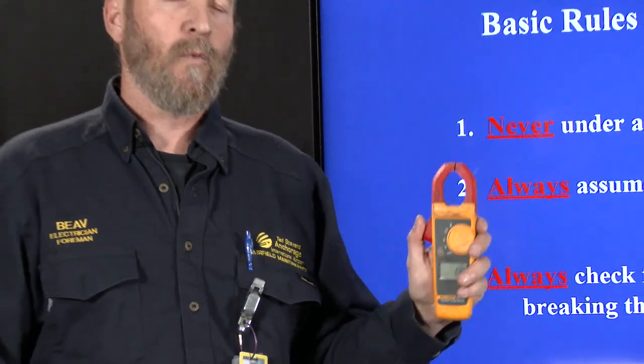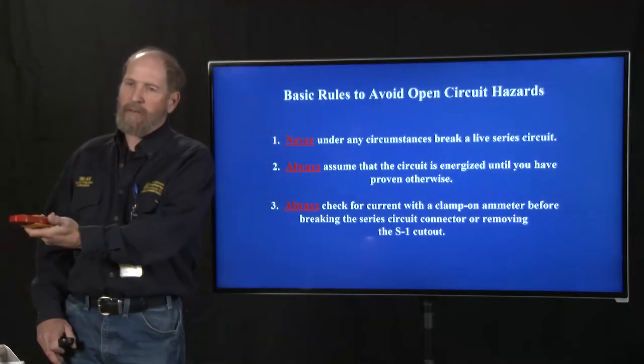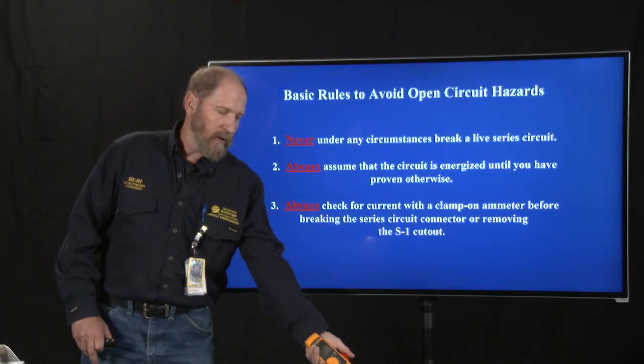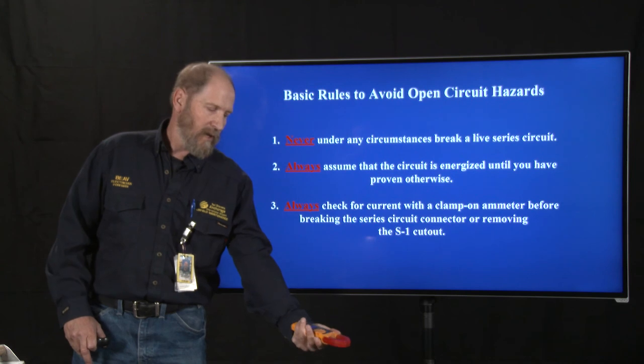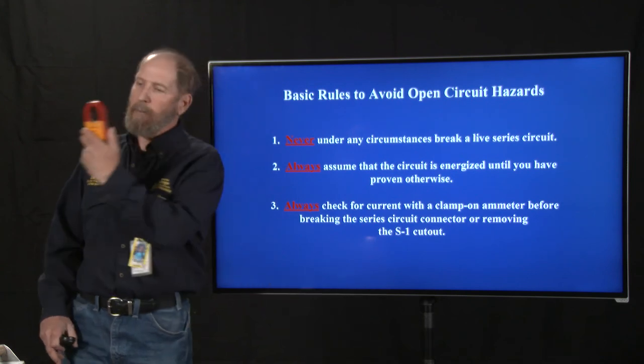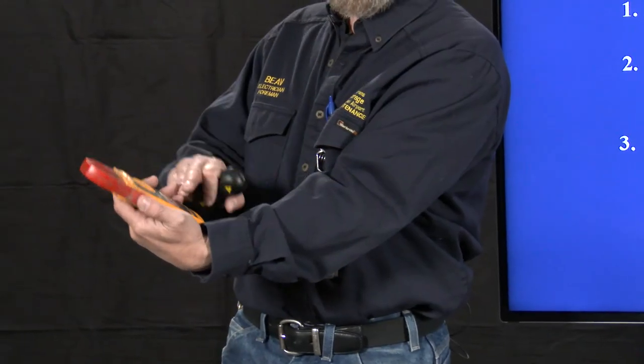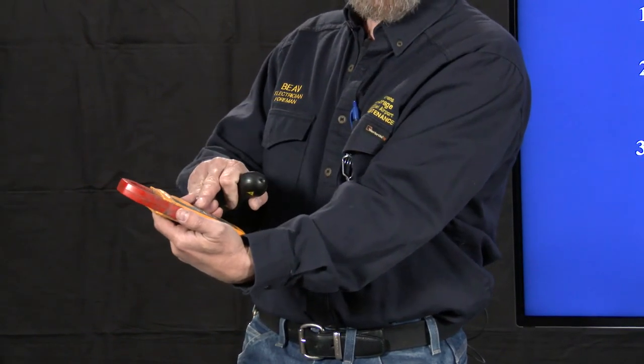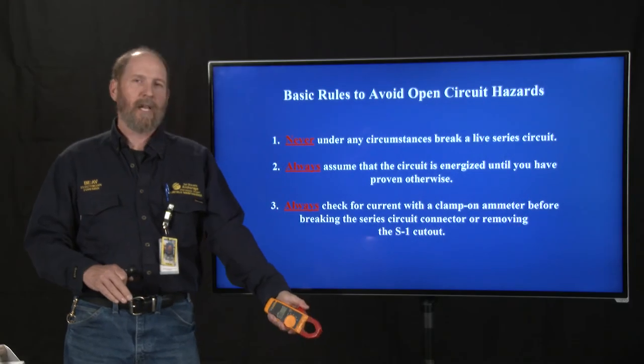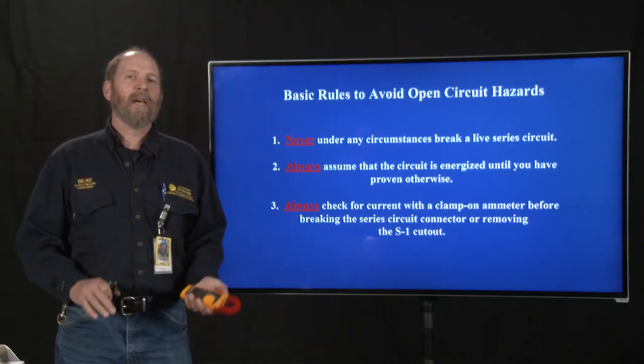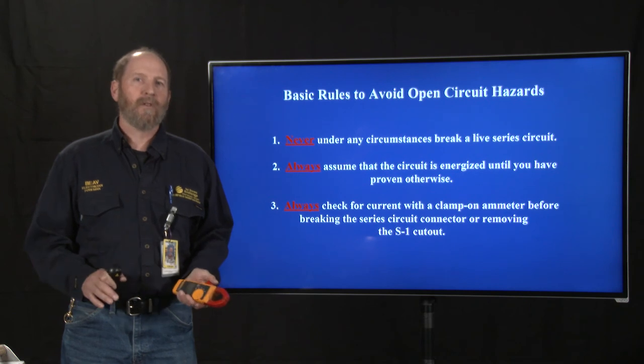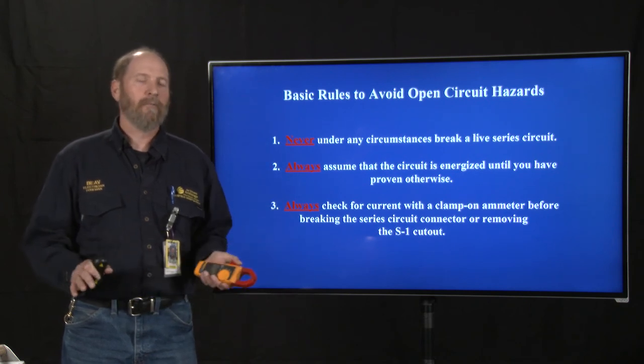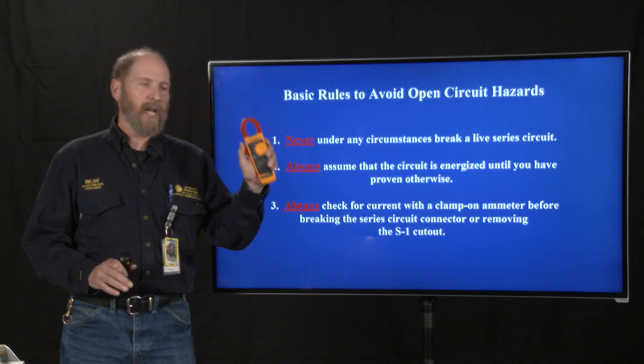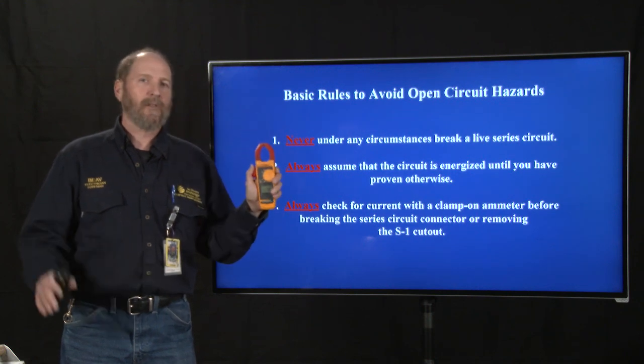So the only for sure way to know your ammeter is working is to clamp onto a live circuit, clamp onto the circuit that you're concerned with, see that there's zero amps, and then clamp onto live again and check your meter and make sure that it's showing amps. Then you know 100% certain that that is dead. And I'll tell you that that is almost impossible to do out in the airfield. You're not going to be able to do that. So it's important that you check your clamp-on ammeter back at the shop once in a while.